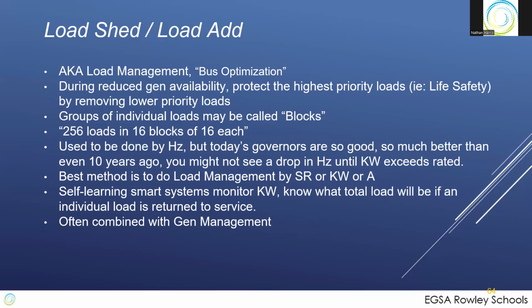So you'll take off your lowest priority loads in order to maintain your highest priority loads. The analogy is the operating room at a hospital has highest priority. It's going to stay on. And some people say it's the boss's coffee pot, but whatever. You maintain your highest priority loads by shedding the lower priority loads. And so once you get more generation back on, so our scenario is you're running 3, you trip 1, now you've got 2 and you need 3. So you start the other 2, get 1 good one, and now you can bring back on all your other load. So load shed and load add often work in conjunction with gen shed, gen add.